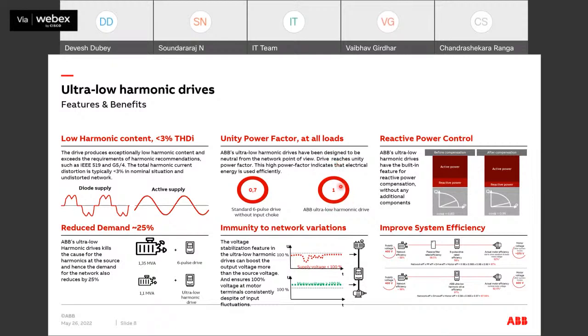There is another feature available in the active front-end drive: it can give reactive power control. That means when you have linear and non-linear loads on the same bus, we can still have reactive power given by the drive to compensate the non-linear loads. We can have a reduction in the transformer size of up to 25% and immunity to network variations. So this technology has a function which can boost the voltage. It can sustain a voltage dip up to a certain percentage.